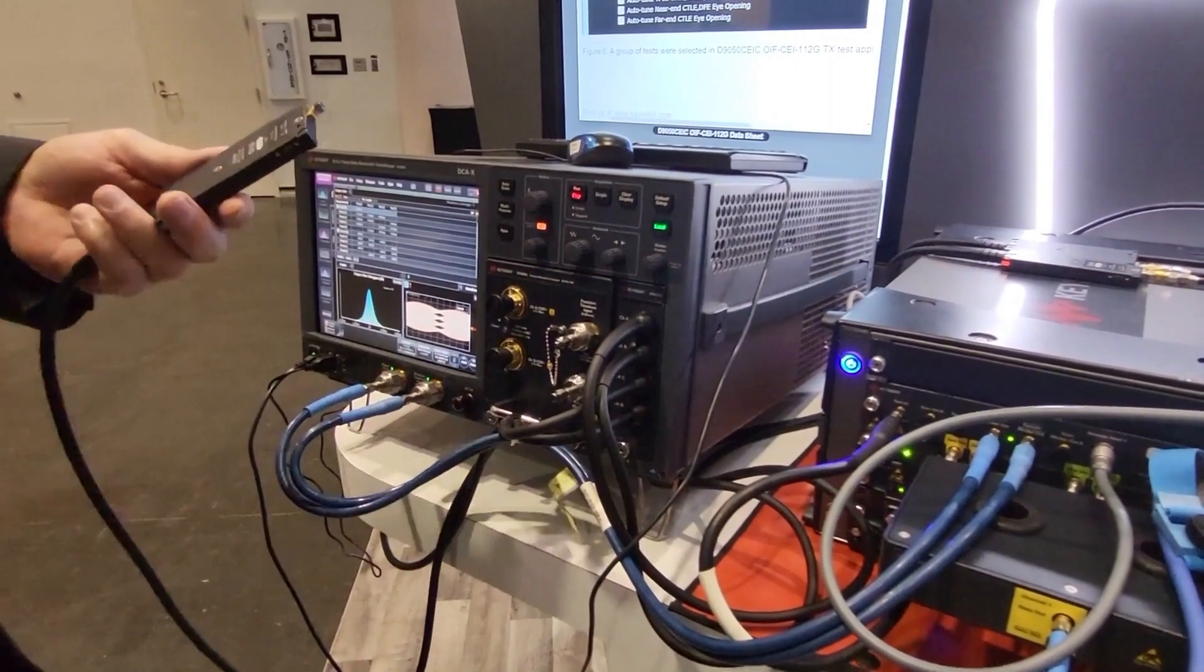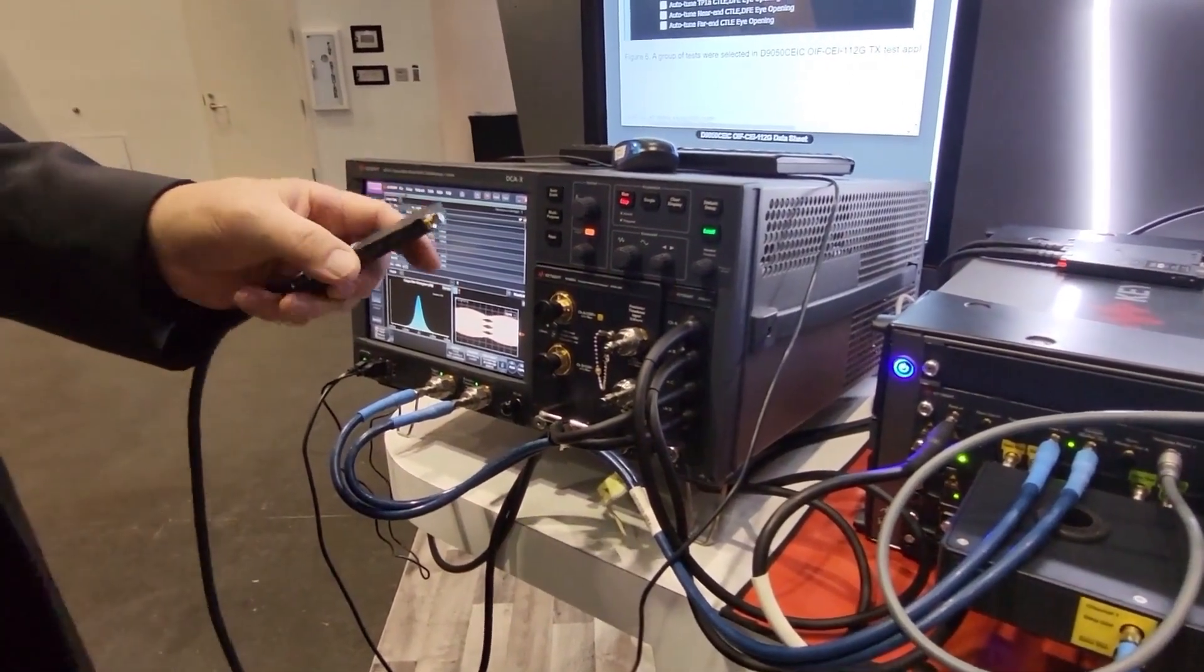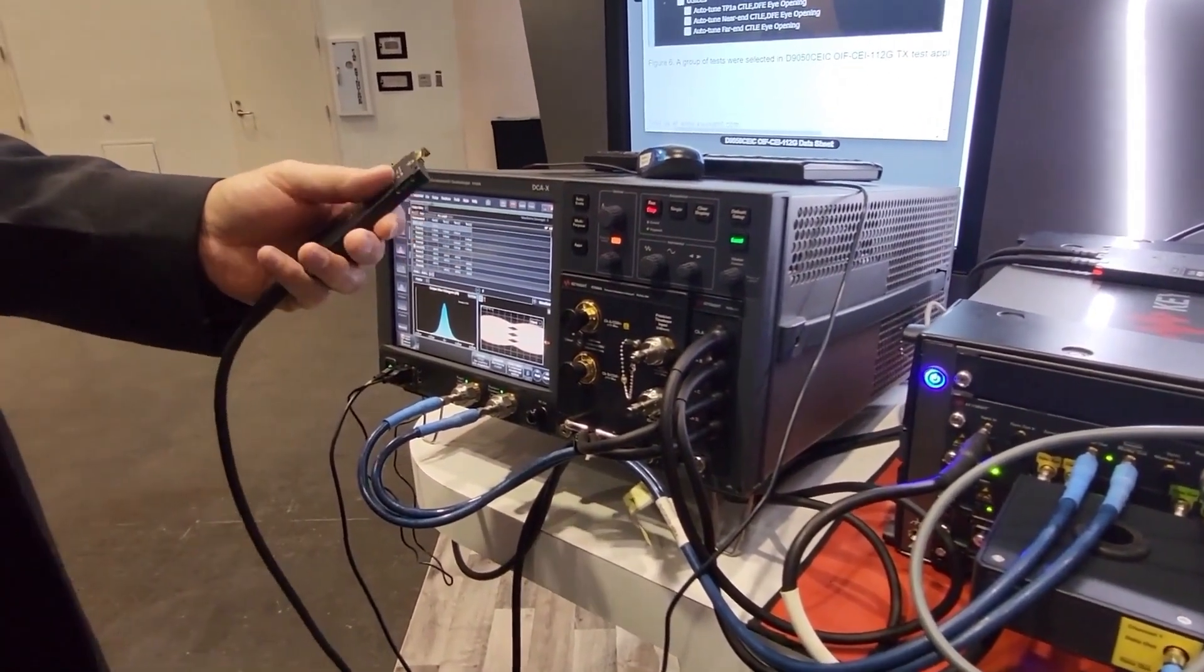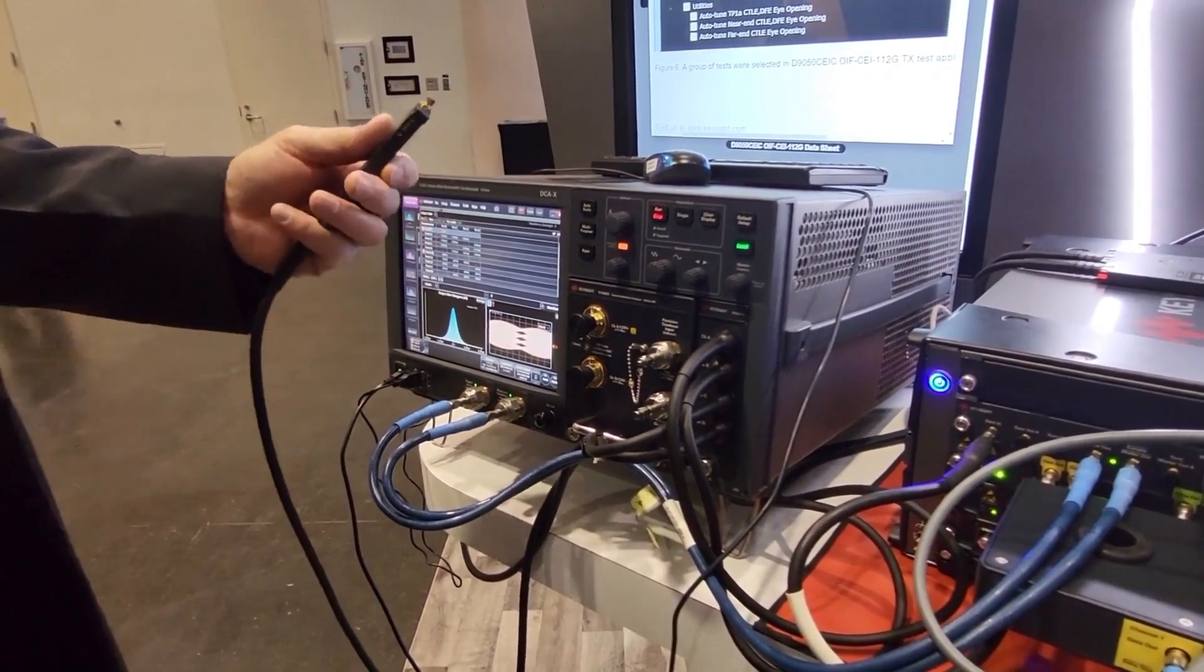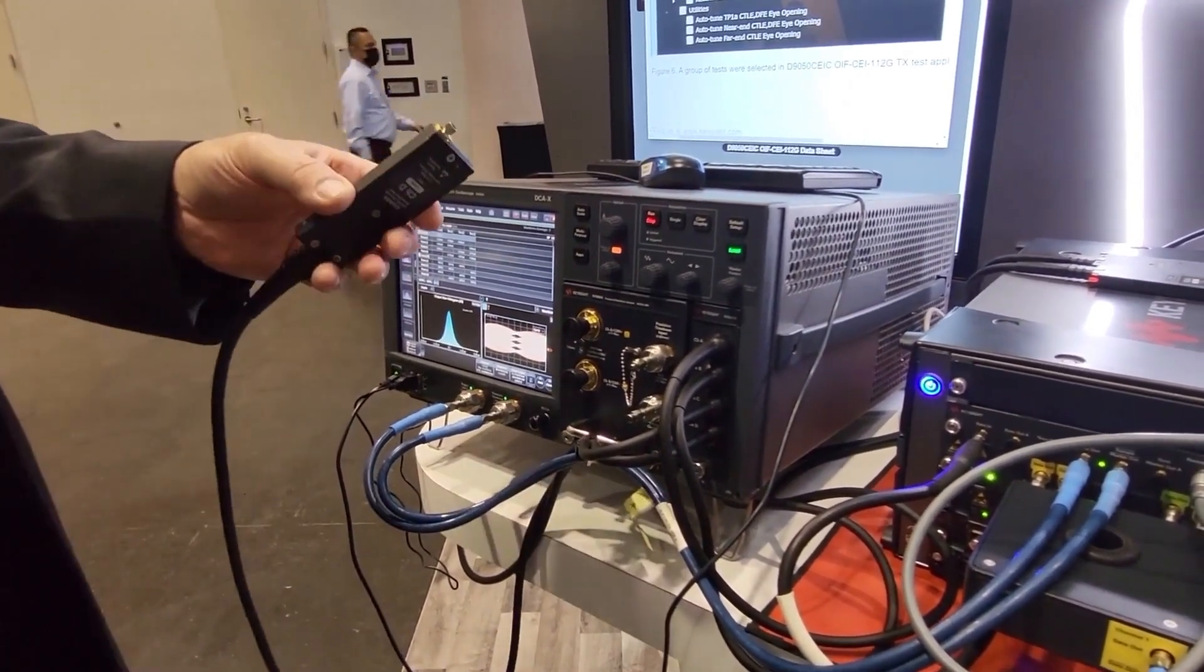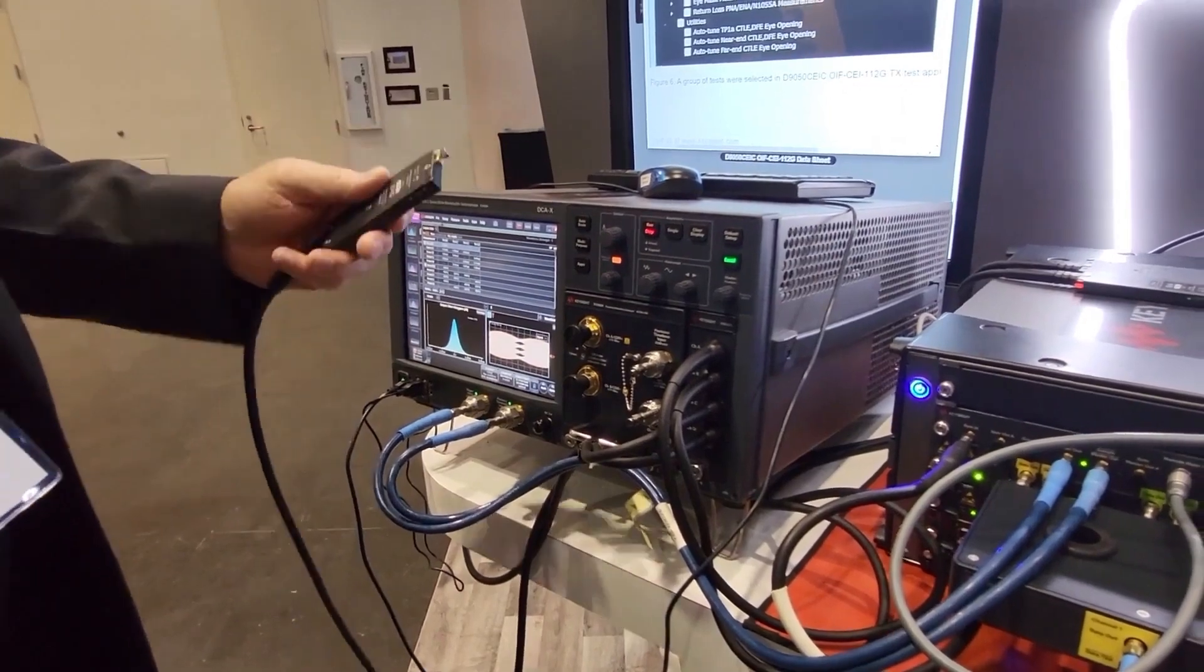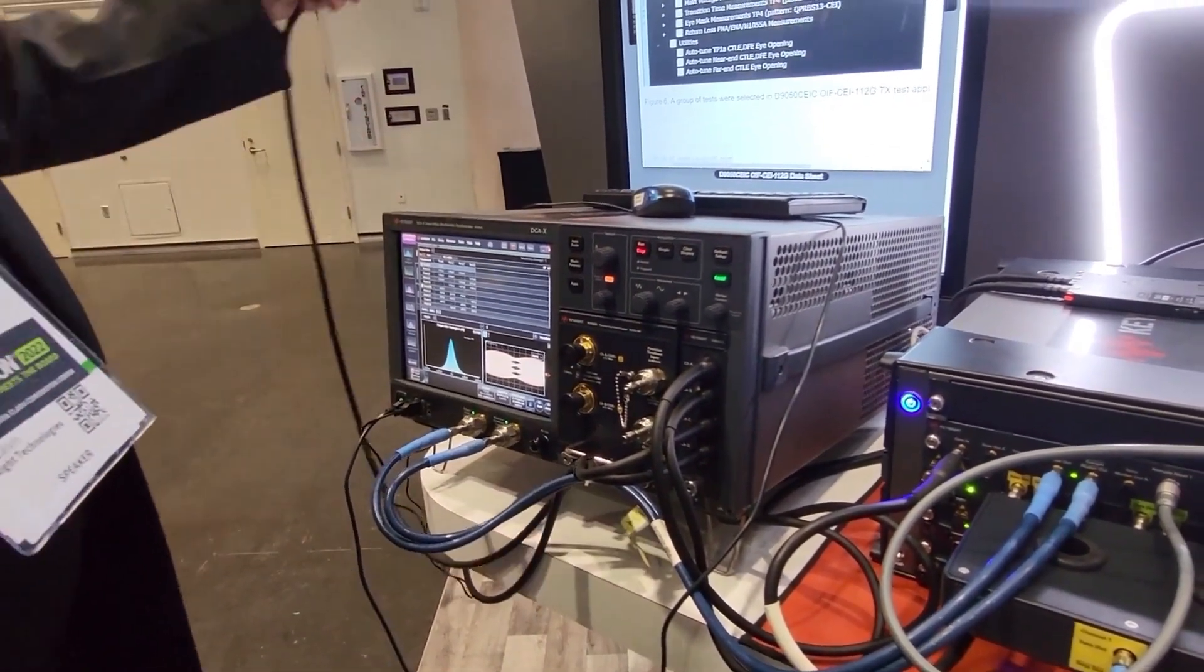The DCA is actually receiving the signals through these 120 gigahertz remote heads we have. They're very handy and popular remote heads for these sorts of applications. It gets you the bandwidth and the noise fidelity you need where you need it close to your device under test.